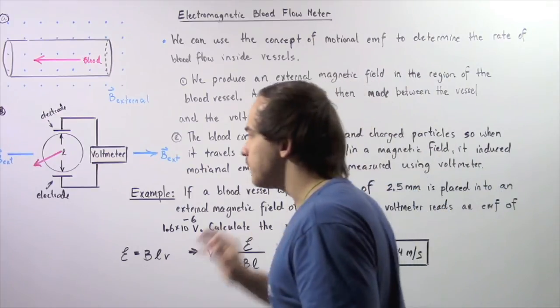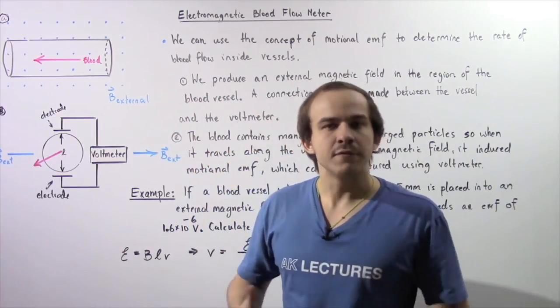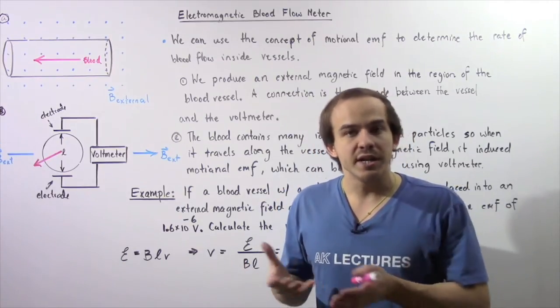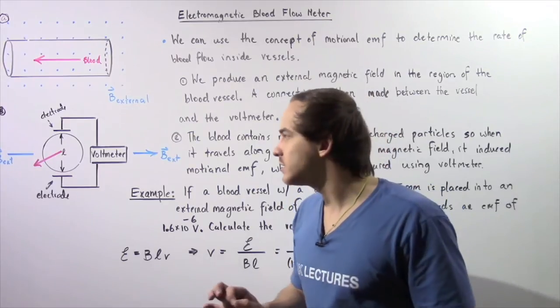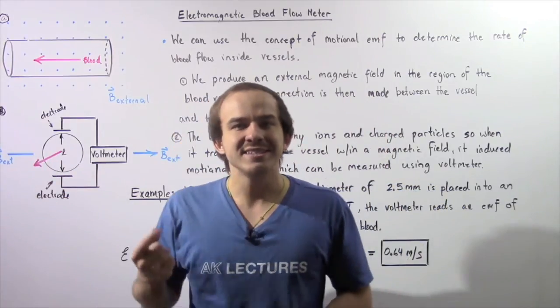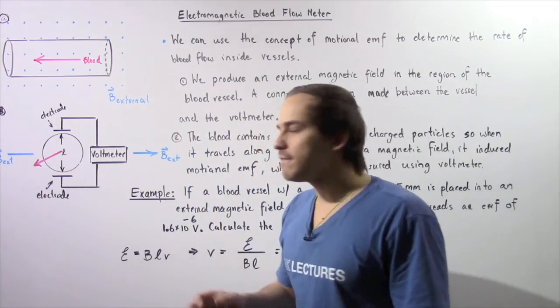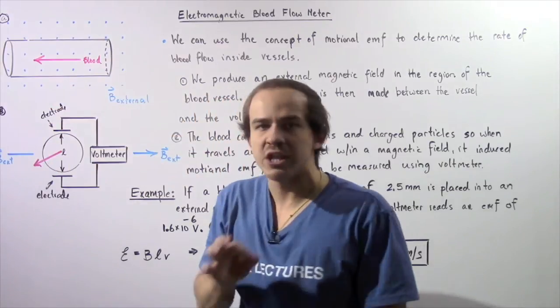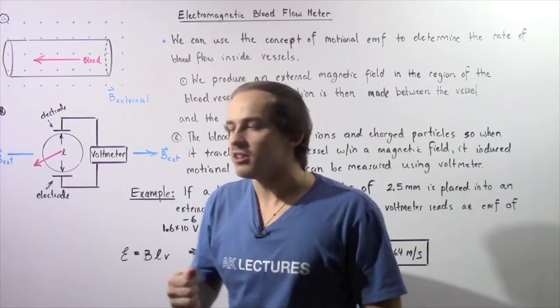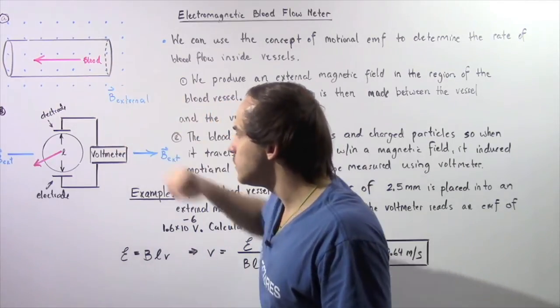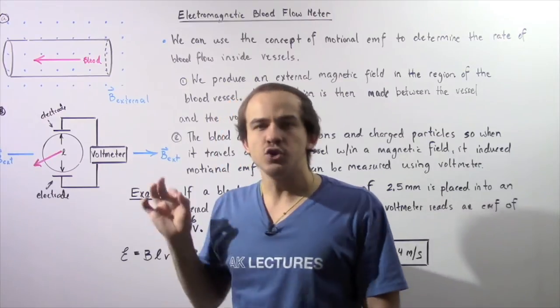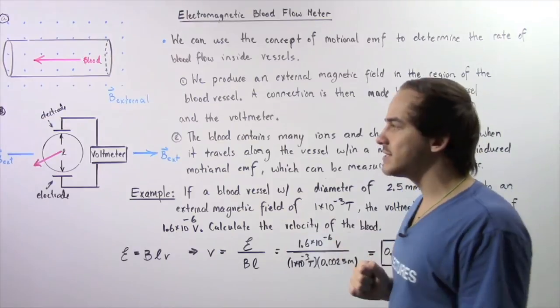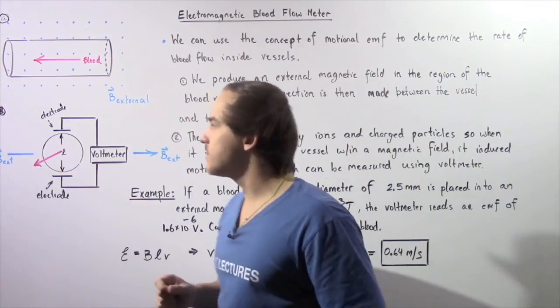As our blood flows, it contains different types of charged ions and charged particles, so the blood acts as if it were a moving conductor. When the blood flows, it induces a Motional EMF inside our wire between the two electrodes. This creates an induced electric current that flows through our voltmeter, and we can use that voltage to calculate the velocity of the blood.